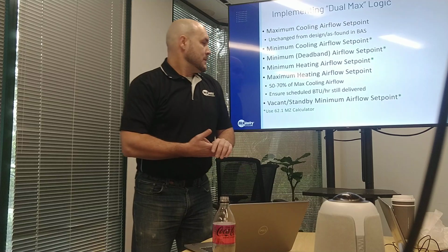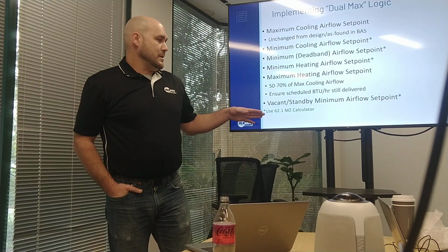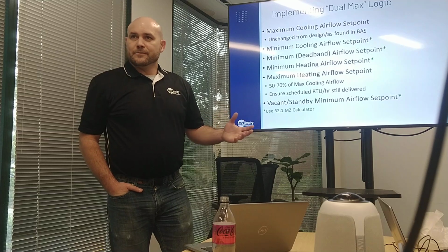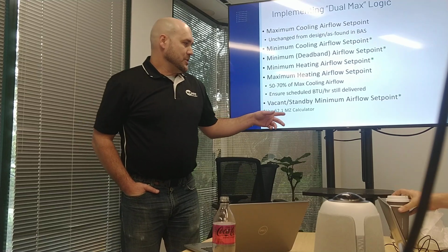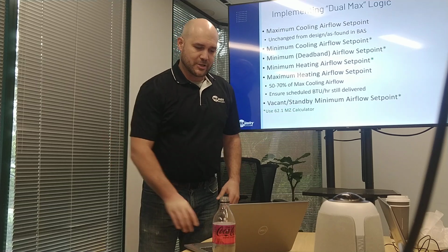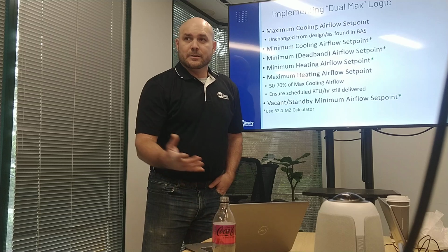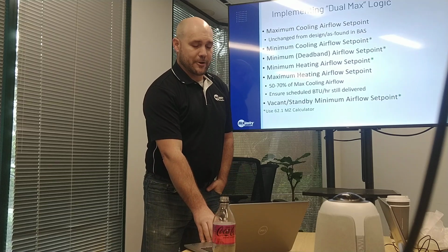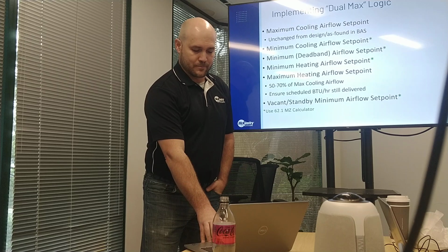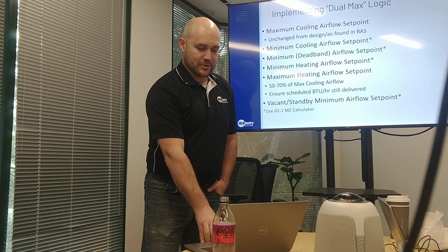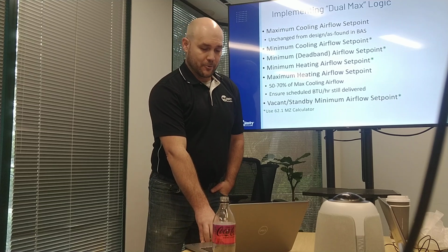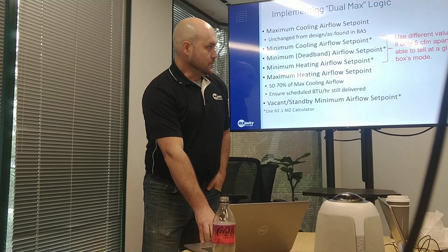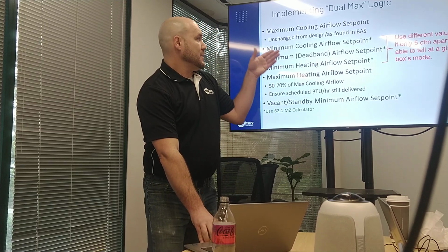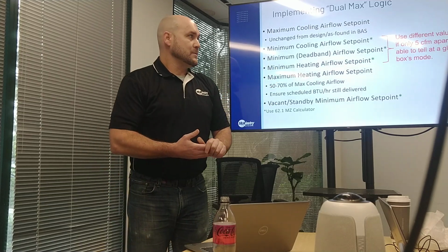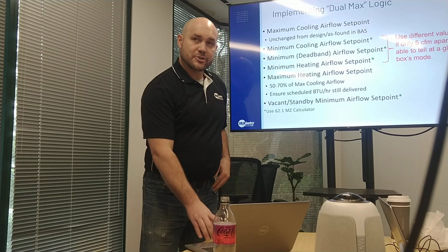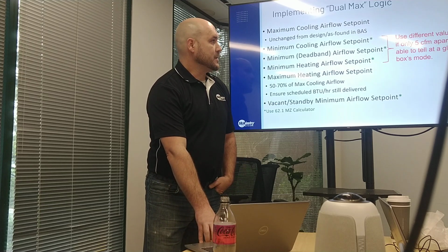So the green asterisk indicates that you should use the ASHRAE standard 62.1, which is the standard for ventilation. They have the multi-zone VAV calculator tool that I have a couple of screenshots of, and it's designed to help you calculate minimum airflows to zones based on however many people are in there and whether it's in heating or cooling. So again, as I mentioned on the last slide, you probably want to keep these three minimums similar but with some distinction between them, maybe 5 CFM apart, to be able to tell at a quick glance.